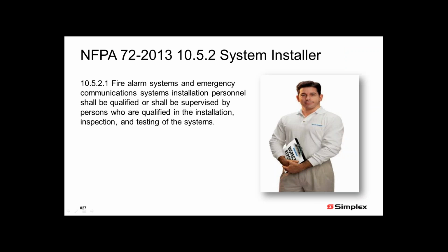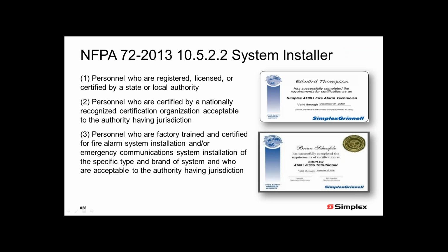So it's the same thing as we have with the designer. In 10.5.2.1, again, the fundamentals chapter, we say that fire alarm systems and emergency communication systems installation personnel shall also be qualified or supervised by persons who are qualified. And it's the same type of process that we had for the designer. Are you registered or licensed by the state or the local authority or the civil defense? Have you gone through a series of testing from some nationally recognized testing laboratory or organization? Or are you factory trained and certified by an entity like Simplex product?